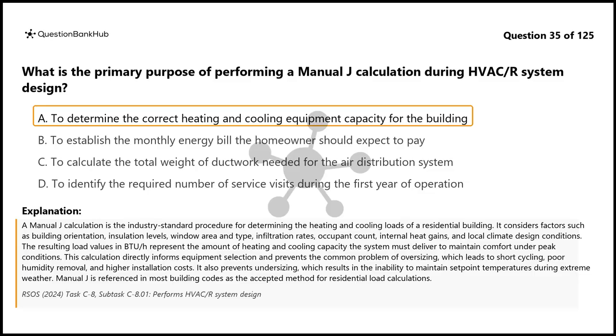The resulting load values in BTU/h represent the amount of heating and cooling capacity the system must deliver to maintain comfort under peak conditions. This calculation directly informs equipment selection and prevents the common problem of oversizing, which leads to short cycling, poor humidity removal, and higher installation costs. It also prevents undersizing, which results in the inability to maintain setpoint temperatures during extreme weather. Manual J is referenced in most building codes as the accepted method for residential load calculations.